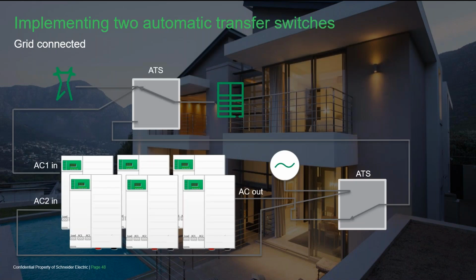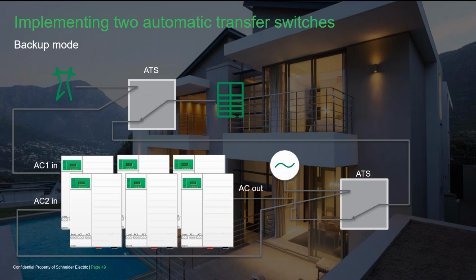If this were a 6-inverter, 3-phase XW Pro system, the transfer relays for AC1 and AC2 will be protected. When the grid is present, the AC loads are served directly and demand is reduced by exporting PV and/or stored energy. Note that when the grid goes down, the ATS will switch to the backup position. The system will continue to run off the batteries until the grid comes back or the batteries get low.